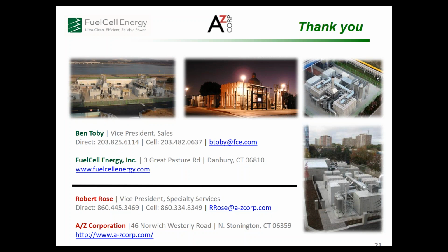Our fuel cell is designed to operate on methane-based fuels, so anaerobic digester gas from a wastewater plant, a food and beverage operation, or organic digestion can be used to power the fuel cell. Anything down to about 50% methane, with the balance being CO2 or nitrogen, works very well. I've got probably 15-20% of those 200 megawatts I cited earlier operating on biogas fuel, on renewable fuel.